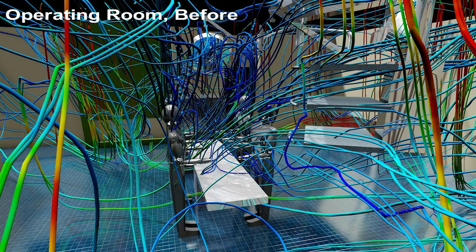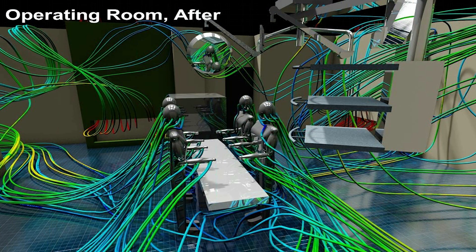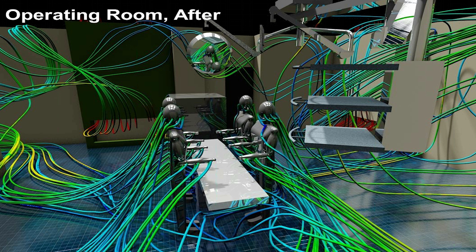After running a couple iterations of the CFD model, tweaking the 3D model, we were able to clean this up and show a much more organized operating room. So in the center of the screen is the operating table and as you can see all of the ventilation is going away from that table and none of the contaminants would be recirculated back onto the patient so that we can minimize the risk of infections post-surgery.